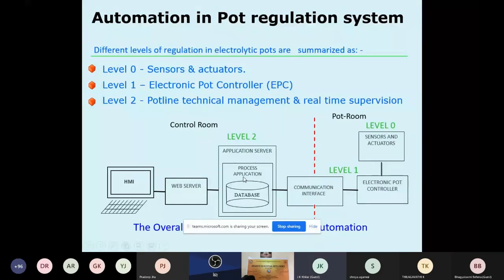And these servers, by means of the web server path, connect to the HMI, the human machine interface. This is situated at level 2, the control room, where there are HMI stations. If any command goes from the HMI to the sensors or actuators, it goes through the web server and the main server, and through the communication interface it goes to the field instruments. So this is an automatic process, and the entire regulation is made by the server. The engineer only takes the reports: day report, shift report, monthly report, quarterly report, like this.